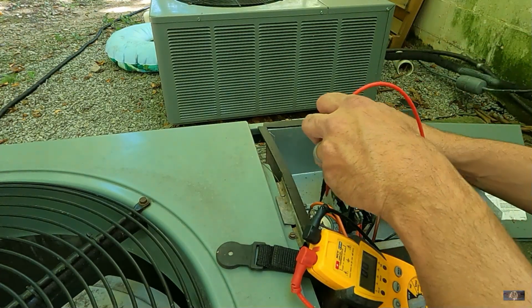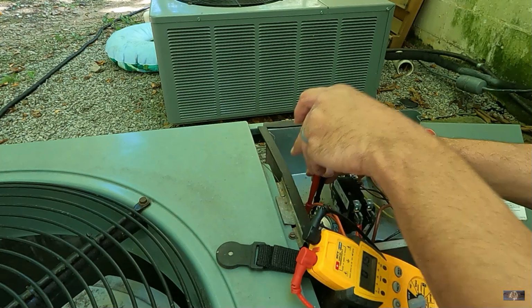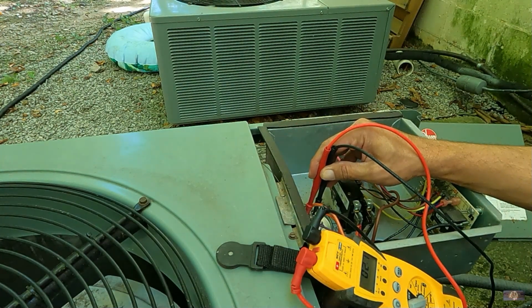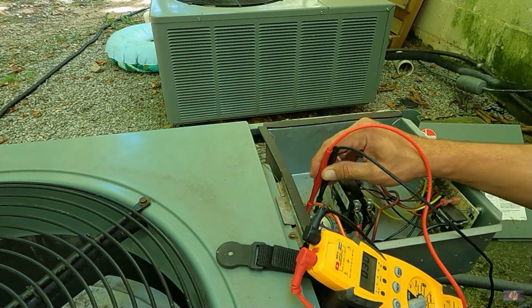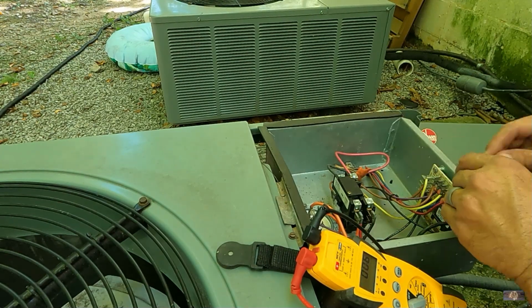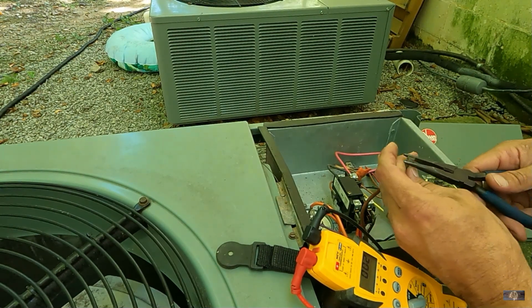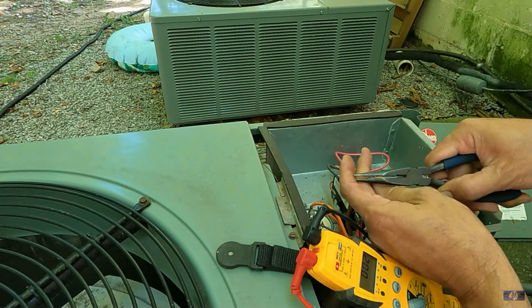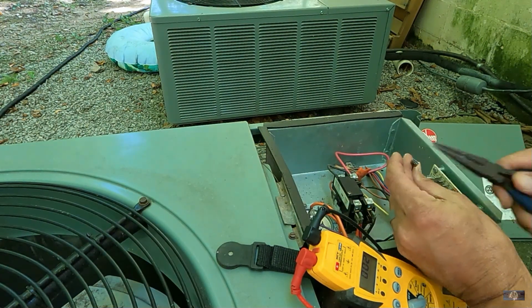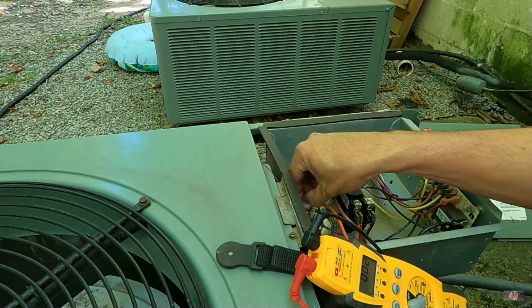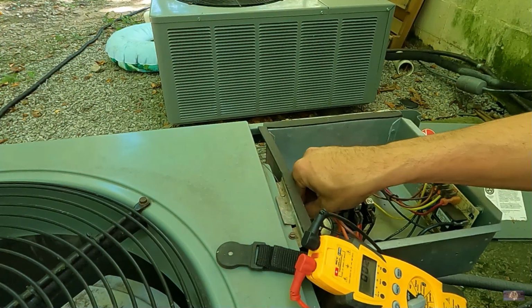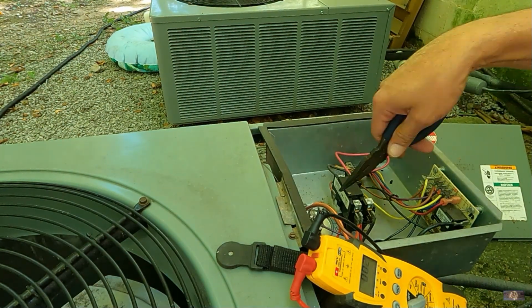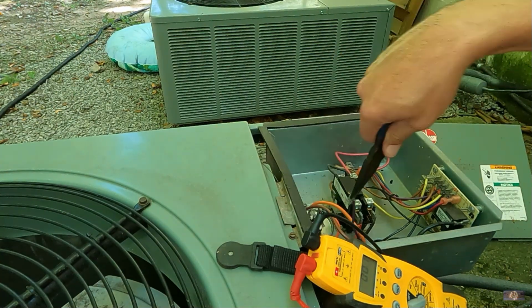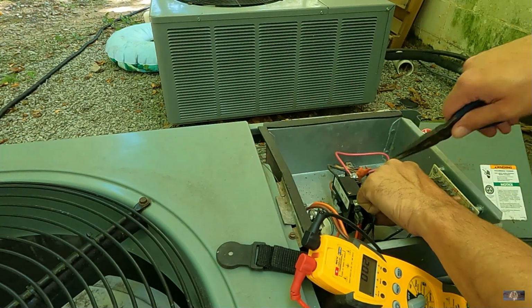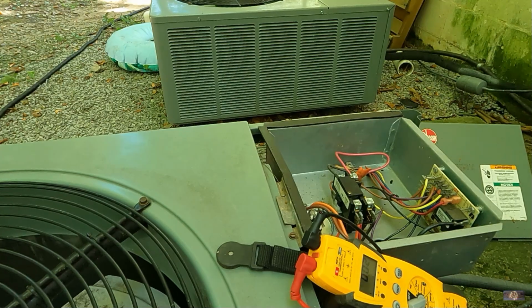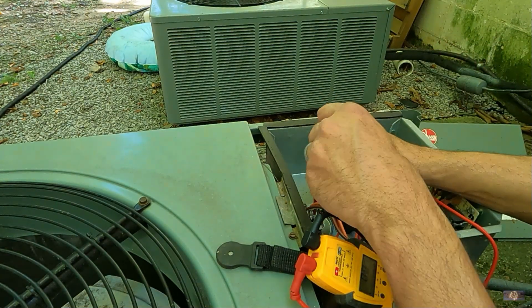Go common to fan. And we got 3 microfarads. Nice. I always like to test, tighten these up before I put them back on. Just pinch the stake on. Sometimes you don't have to. It's just good practice. Yeah, that way they go on nice and tight. Go ahead and check the Herm side next here. Now this should be a 35, so go ahead and see what this one's doing.